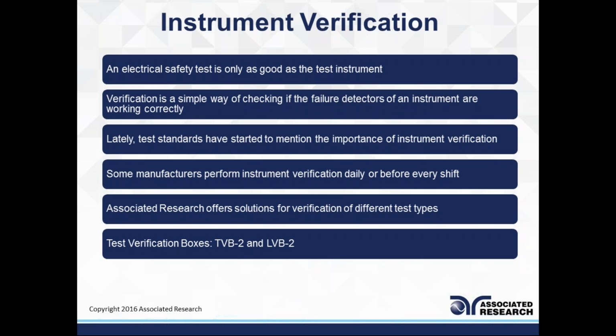And some people like to verify an instrument every time. We've run into applications where customers perform the verification test on their test equipment anytime they use it. So every time they power it on, they run a verification test just to have peace of mind that the instrument they're about to use for testing is functioning properly.